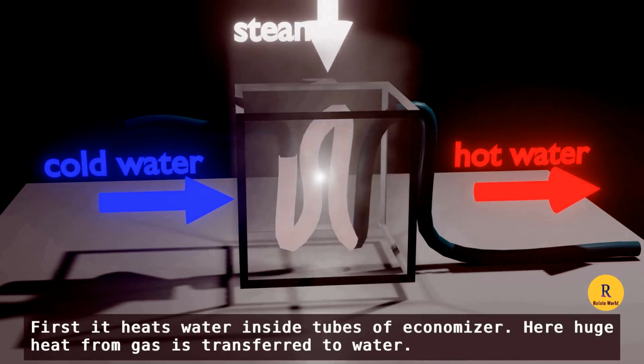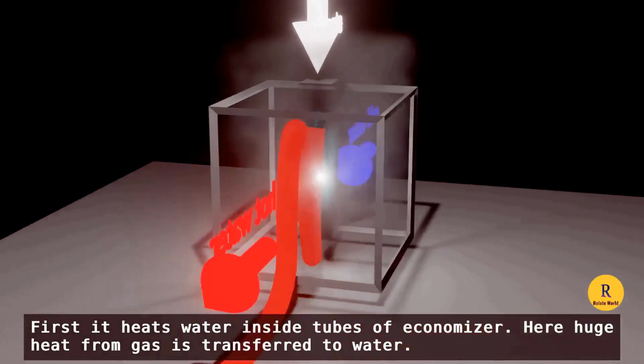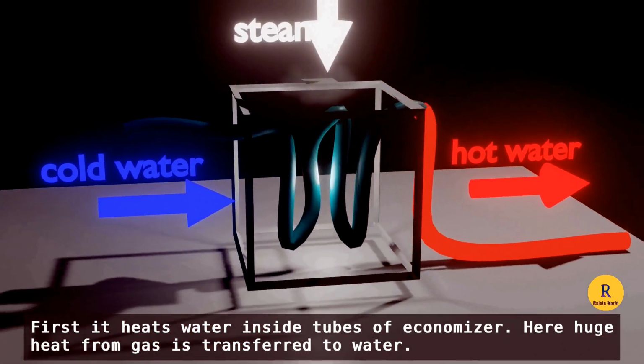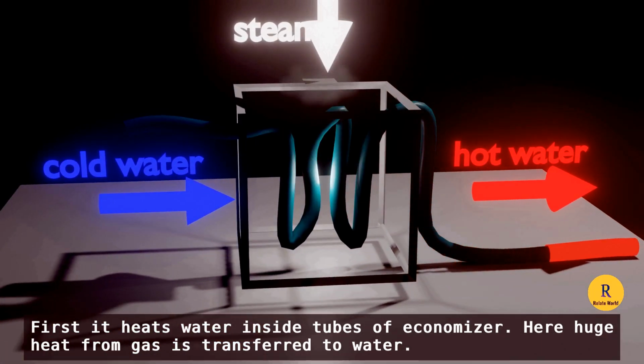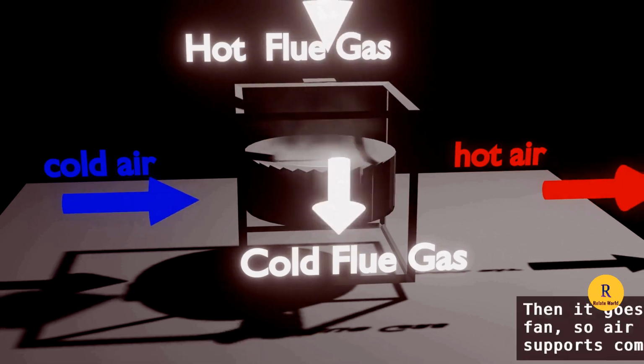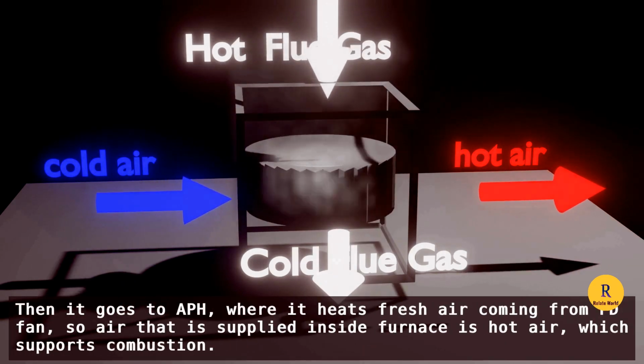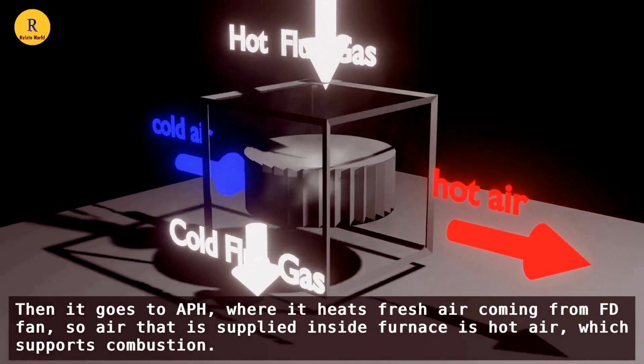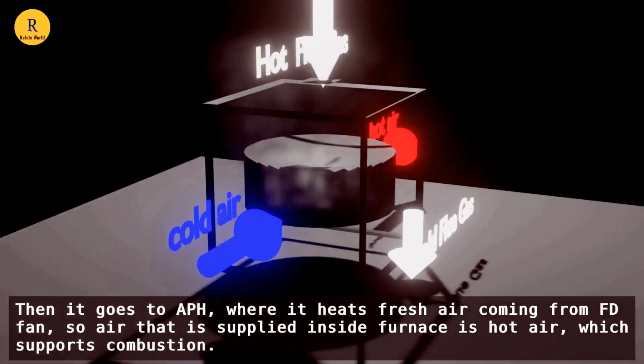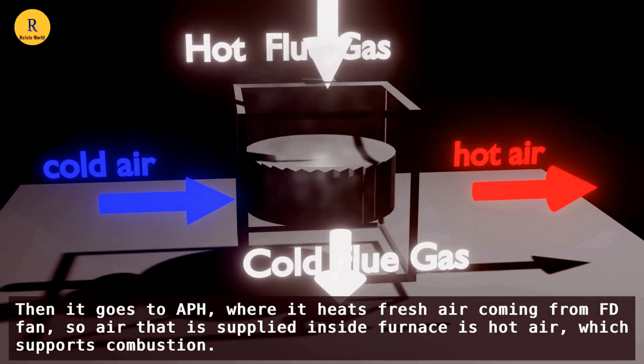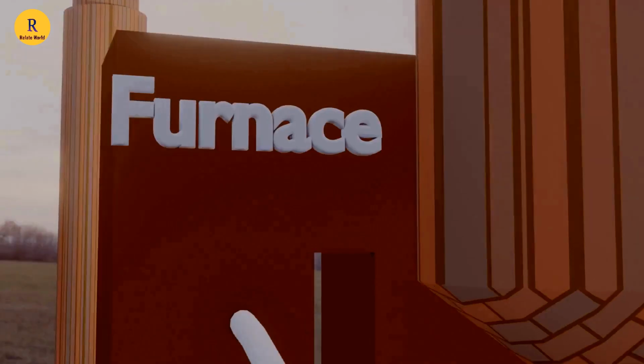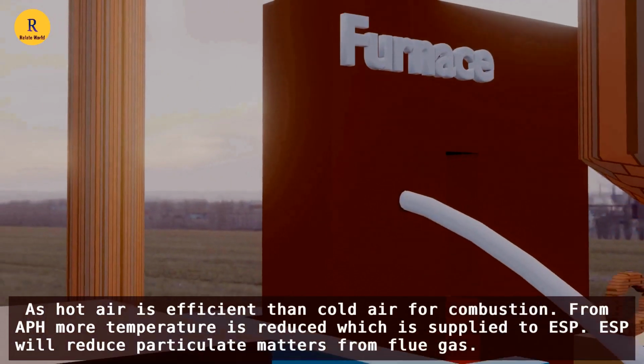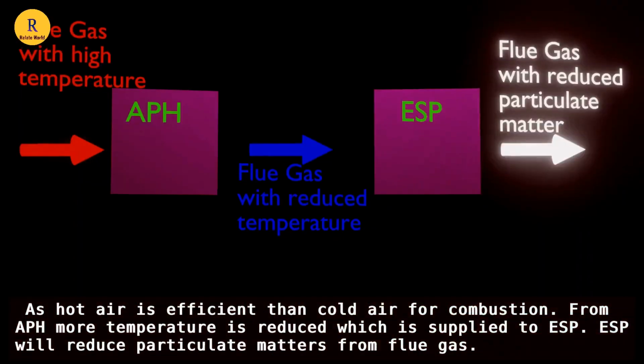First, it heats water inside tubes of economizer. Here, huge heat from gas is transferred to water. Then it goes to air preheater where it heats fresh air coming from FD fan. So air that is supplied inside furnace is hot air. It supports combustion, as hot air is more efficient than cold air for combustion.